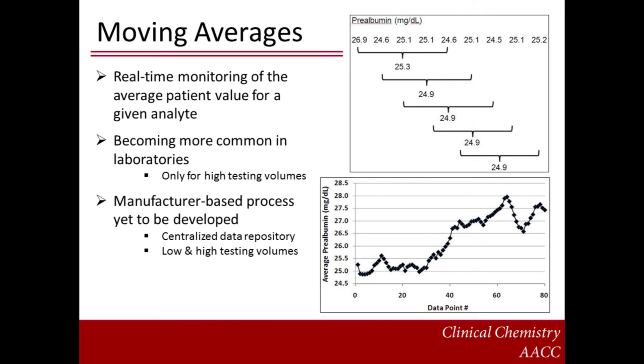Moving averages can be performed either at the level of individual laboratories or by the manufacturer through a centralized real-time repository for patient results. While many laboratories are now implementing patient moving averages, a manufacturer-based patient results repository is yet to be created. This latter system is particularly attractive because it could flag questionable reagent lots within hours after entry into the market and would also benefit laboratories with low testing volumes that don't benefit from the local implementation of moving averages. For more information on moving averages, consult references 7 through 9.